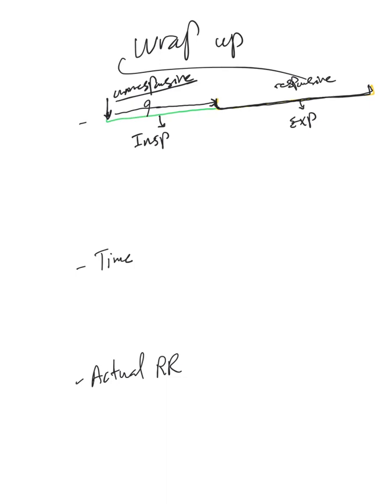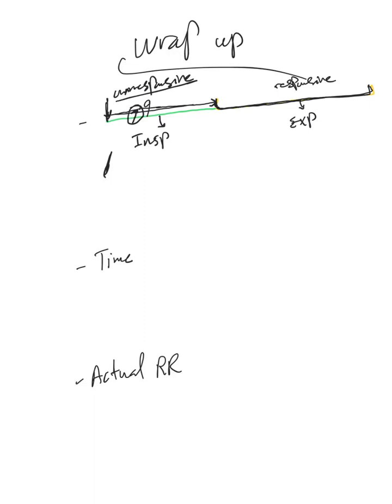During inspiration, the ventilator is unresponsive to trigger. Once it receives the first trigger and initiates the breath, the ventilator becomes unresponsive until it finishes the breath and goes into expiration again. That's very important. So if the patient initiates a breath here and the ventilator delivers the breath, another breath initiated here will be ignored. Only if it comes here will it be picked up again by the ventilator.